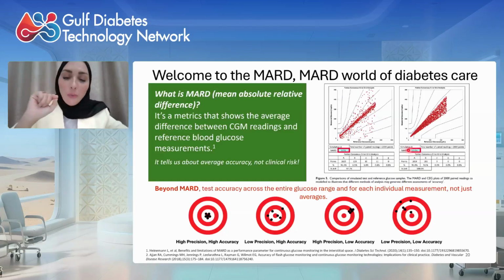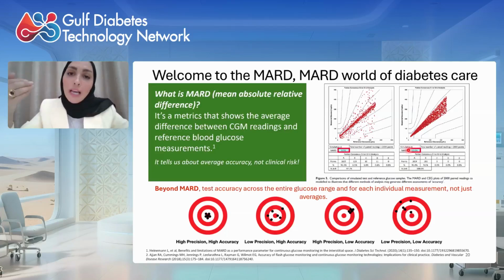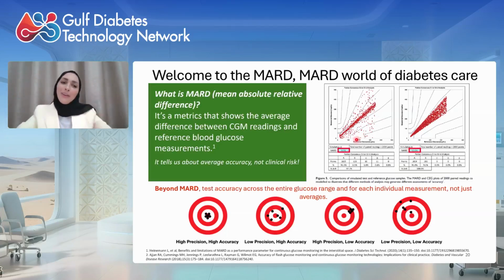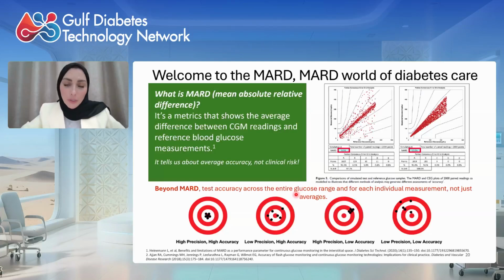So I want every one of you now not to depend on MARD anymore. If any company introduces their device and tells you our MARD is 8, go back and check for excursions, go back and check the adjusted MARD, which is the real MARD after they adjust for the outliers. So now we need to see the accuracy beyond the MARD. Test the accuracy across the entire glucose range and for each individual measurement, not only the average of the accuracy. In fact, we need to look into the data.